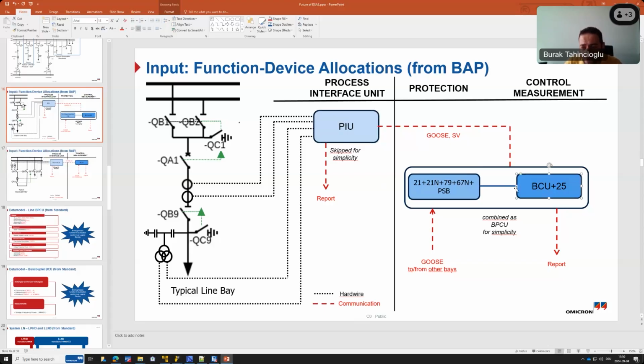And then you might have possibly 2 independent protection IEDs and 1 separate control unit. But this is completely up to design. Any utility can decide any number of boxes, or you can put everything in one box. Of course, reliability concerns make it possible to have redundancy mechanisms, also device redundancy. Then we would end up with 2 protection units, 1 bay controller, or even 2 bay controllers, and maybe 2 PIUs. I can answer only from my personal experience, but there must be many more variants and flavors of this. Mm-hmm.